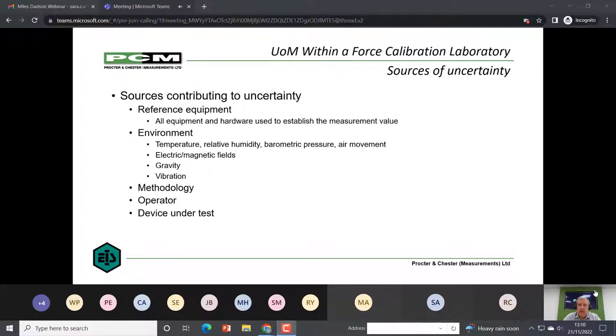What causes the uncertainty with regard to a measurement? It is all the reference equipment that you're using to establish that measurement value, and depending on the different types of calibration facilities and equipment, there could be just a few, and we'll come on to those very shortly, or there could be quite a lot. Also, the environment has a very large impact on the measurements that you will take, which is why when you get into most calibration laboratories, it's a very tightly controlled environment. Then there's the methodology that is going to be used to calibrate. You've got various different standards available, and each will have their own little nuances about the way in which you conduct the calibration.